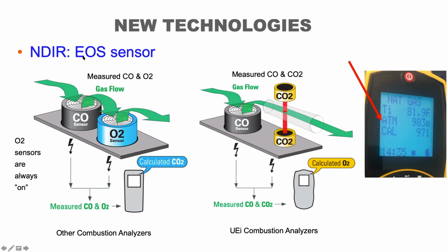And they call it the electro-optical sensor because it uses electronics and optics in order to detect the gas. NDIR stands for non-dispersive infrared. That's the way the sensor technology works.